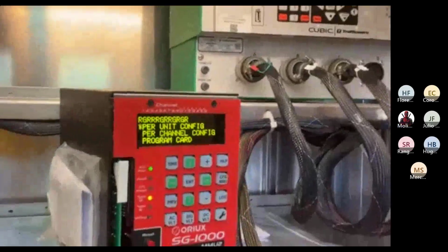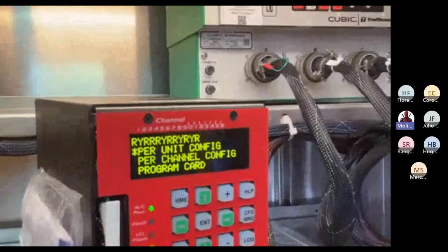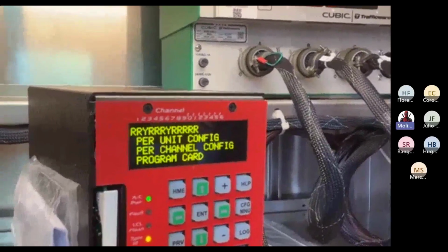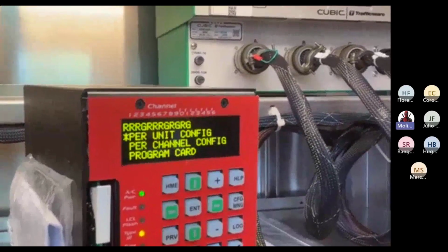Right. So if they had the BIUs, then it'll be a type 16. And you can physically change that. So in cabinet design, there's a terminal called Type Select, right? That they added into TS2 back panels, the ones that are meant to use BIUs and SDLC and all that stuff. So the monitor is looking at that one. If it doesn't see that, it defaults to a type 12. If it does see it, it defaults to a type 16.